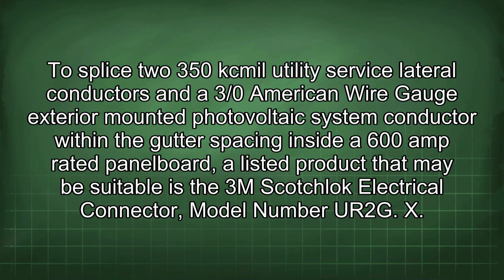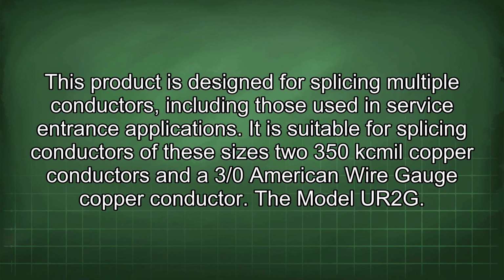To splice two 350 kcmil utility service lateral conductors and a 3/0 American wire gauge exterior-mounted photovoltaic system conductor within the gutter spacing inside a 600 amp rated panel board. A listed product that may be suitable is the 3M Scotchlok electrical connector, model number UR2G. This product is designed for splicing multiple conductors, including those used in service entrance applications.